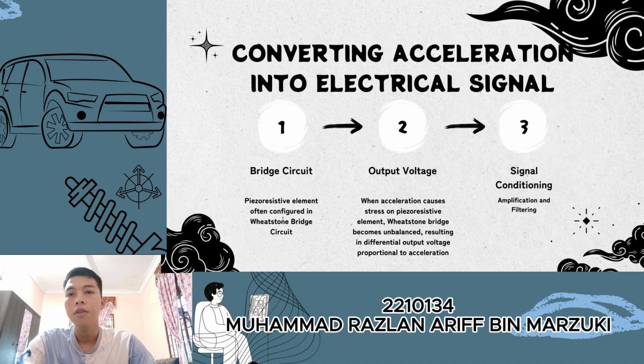Next, we proceed with converting acceleration into electrical signal. Bridge circuit. A key component in the piezo-resistive accelerometer is the Wheatstone bridge circuit. The piezo-resistive elements are configured in a Wheatstone bridge circuit. This configuration helps in measuring small changes in resistance with high accuracy. After the bridge circuit, we then go through the output voltage. When acceleration causes stress on the piezo-resistive elements, the resistance change unbalances the Wheatstone bridge, resulting in a differential output voltage that is proportional to acceleration.